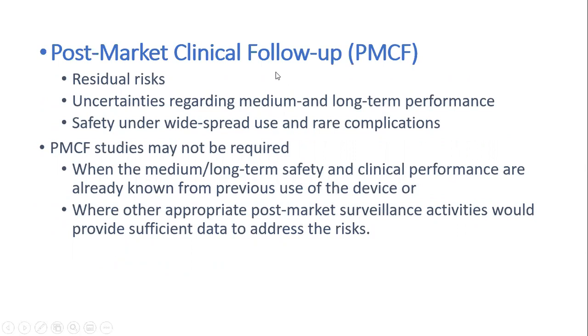If you find any residual risk, or there is uncertainty regarding medium and long-term performance, safety under widespread use, and rare complications, we have to go for PMCF activity. PMCF activity may not be required if medium or long-term safety and clinical performance are already known from previous use of the device.